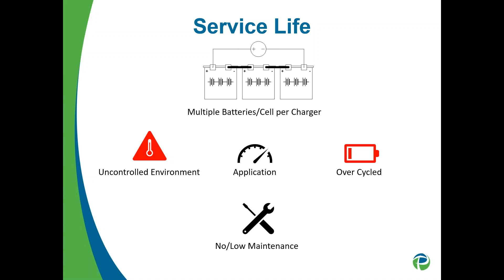Another thing that affects service life is low or no maintenance. When the VRLA battery came out, it was called a maintenance-free battery - you didn't have to fill it, but we still know we need some kind of maintenance, either on a quarterly or semi-annual basis. If you're not doing anything, you can run into those problems and not even know it.